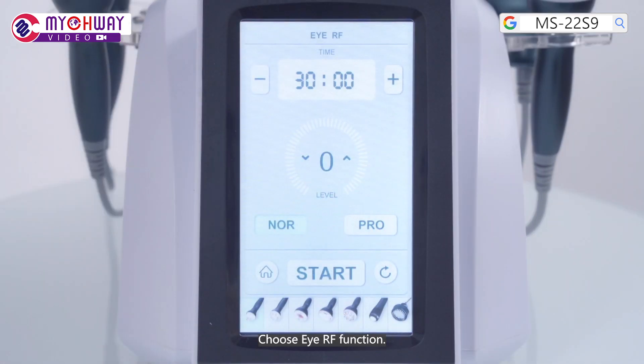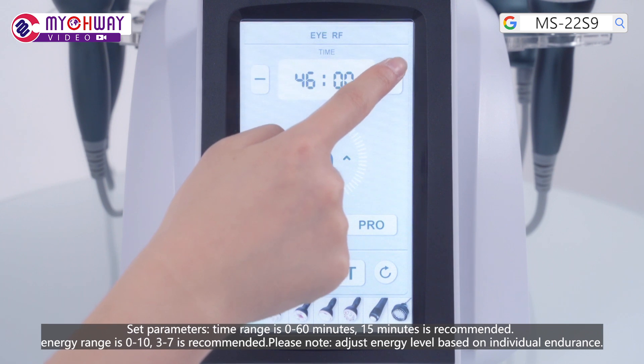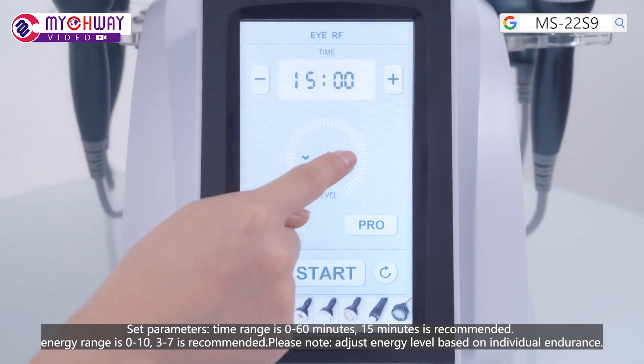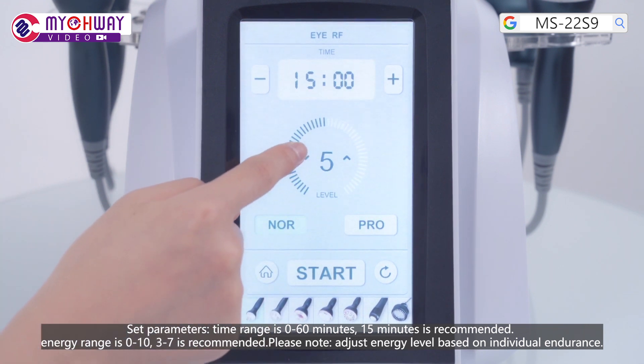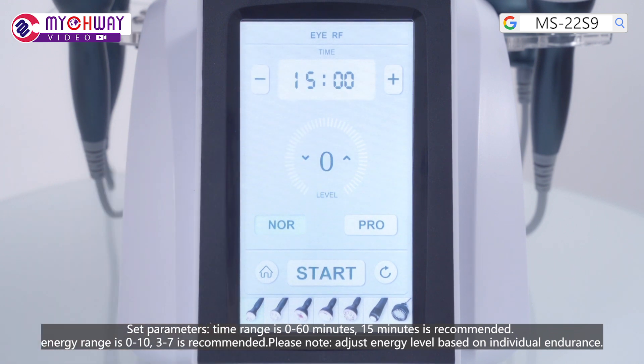Choose the Eye RF function and set parameters. Time range is 0 to 60 minutes; 15 minutes is recommended. Energy range is 0 to 10; 3 to 7 is recommended. Please note: adjust the energy level based on individual endurance.